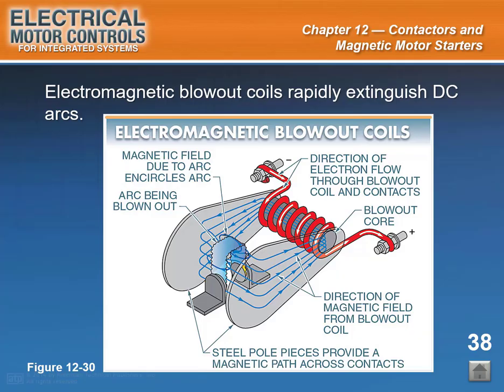The net result is an upward push that quickly elongates the arc current so that it breaks or blows out. An electromagnetic blowout coil is often referred to as a puffer because of its apparent blowout ability. Actually, it just elongates the ion pathway until it becomes so long that there is not enough voltage to sustain the arc. End of slide 38.